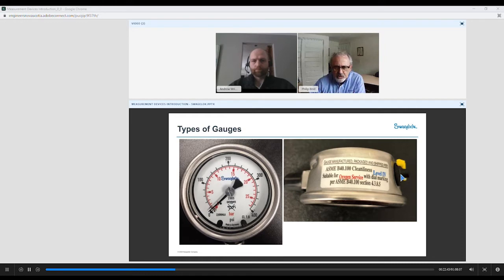Something else I'm just going to point out on this slide. We can see this little valve here. The little valve is used if this gauge were shipped, and I've had it set here, you can see it's not right down to zero. So this will relieve pressure from inside the case. So if this gauge has been on an airplane, flown across the country, and it builds up pressure inside the case, you can get a reading on the dial when you receive the gauge. By simply cycling this little lever back and forth, you will allow that to vent excess pressure in the case and then seal it up again.